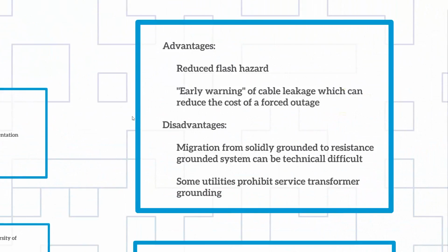But the vast majority of the universities that I've been on that are spread out over campuses, I know about 15 years ago I helped design and modernize the University of Ohio in southern Ohio. And they were 12.47, probably 40 MVA of load back then, and spread around in terms of what they can do. And they were all solidly grounded with fuse switches everywhere, and I was trying to get them to change to start doing some things to give them more reliability. And we actually went through some of that analysis. I don't know if they actually implemented the grounding, but I wanted to go to a resistance grounding.